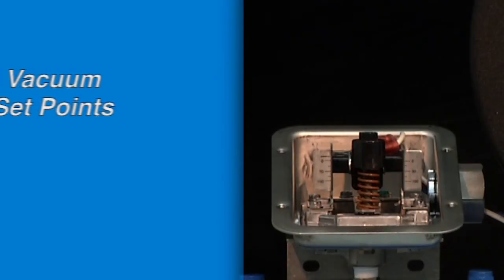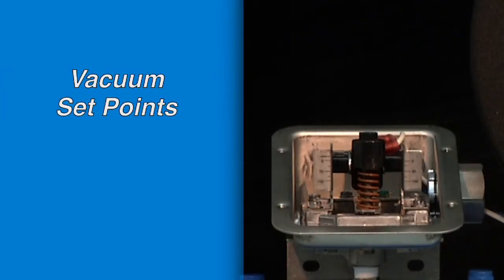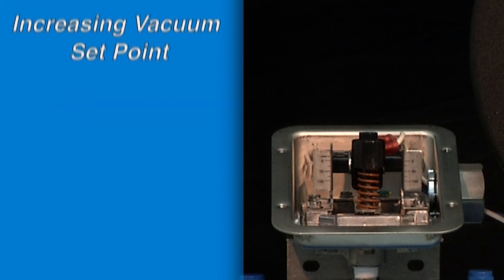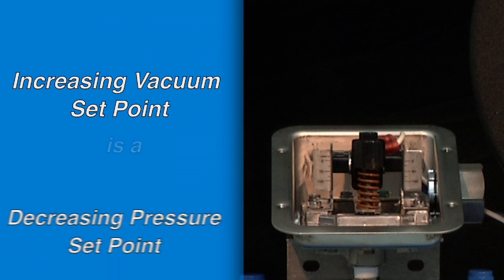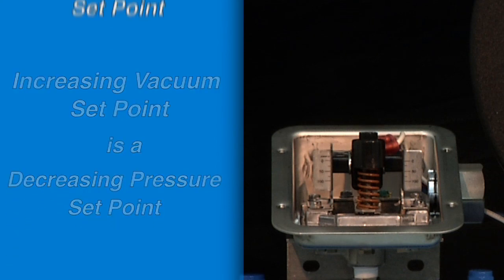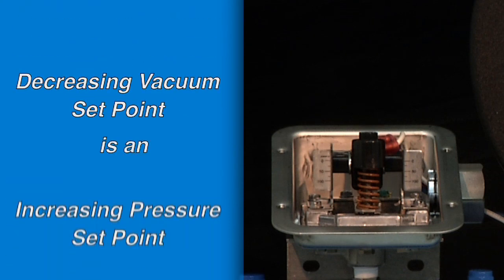For set points on vacuum range switches it is best to think of the set point as a negative pressure. So an increasing vacuum set point is a decreasing pressure set point and a decreasing vacuum set point is an increasing pressure set point.